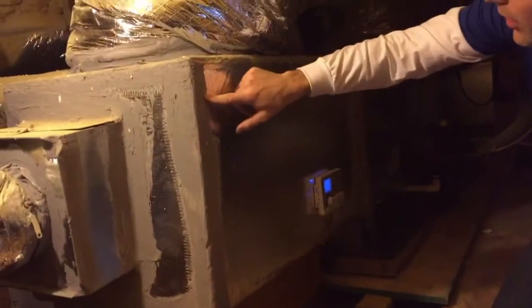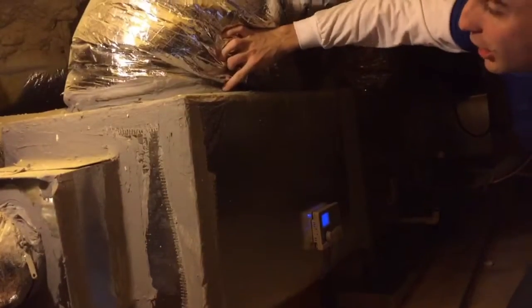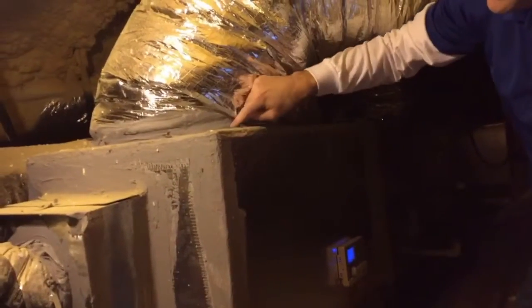Another common issue that can affect airflow is duct leakage. So when I come up into the attic, I want to make sure that all of the seams here are properly masticed wherever there's tape. These starting collars are going to be masticed on the inside of this mastic. This mastic here is actually just a vapor barrier. Inside here, you're going to want your air barrier properly sealed as well. On the return side and the supply side, obviously this is the return side, but it matters even more so from an airflow perspective on the supply side.